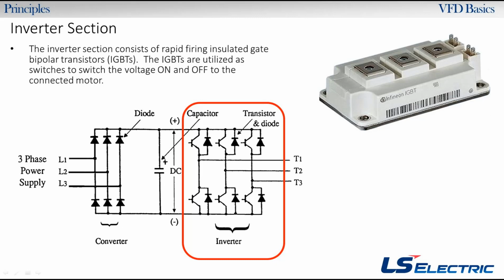So looking at the output here, we have T1, T2, and T3, or UVW, whatever you're used to. This is where your motor would be connected, okay? So we have our DC, and then we're sending that to all these IGBTs, these transistors, and what we're doing is we're actually chopping up that DC voltage, and we're reconstructing an AC waveform. And I'll show you guys that on the next slide.